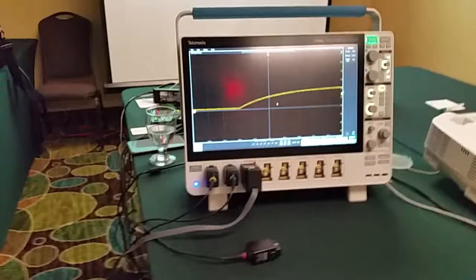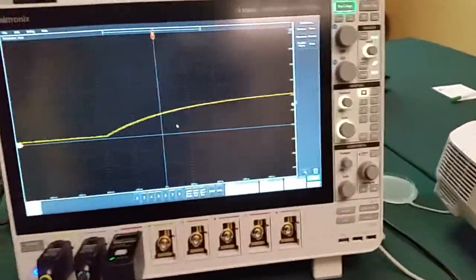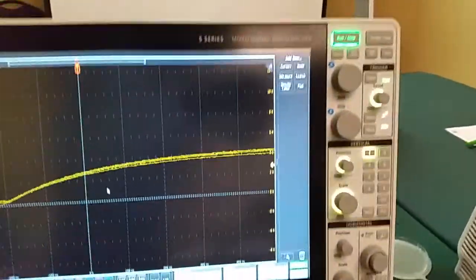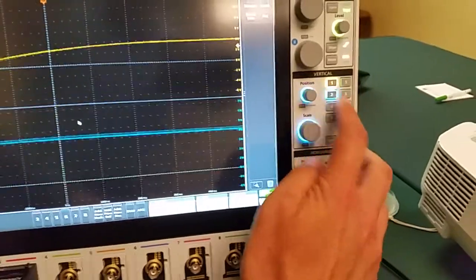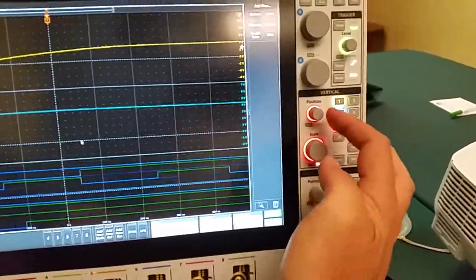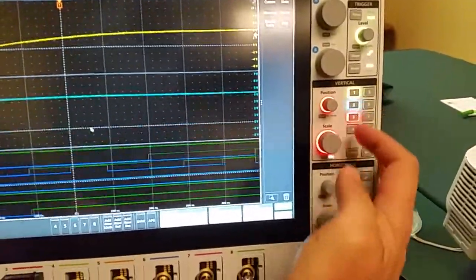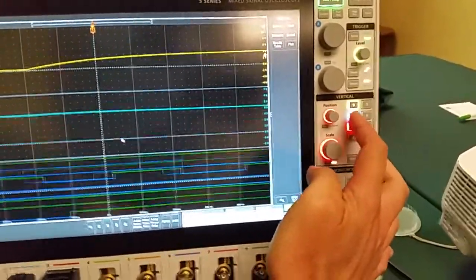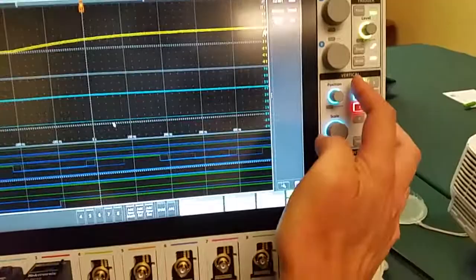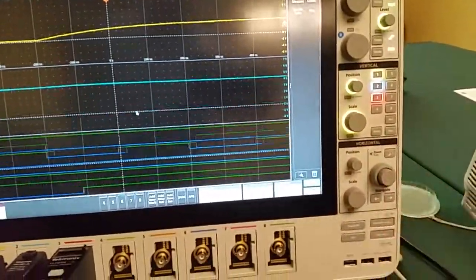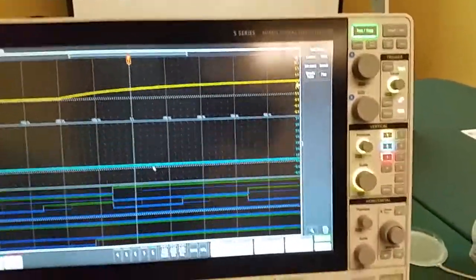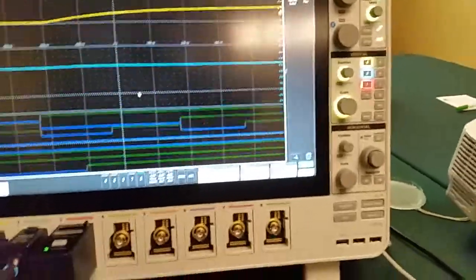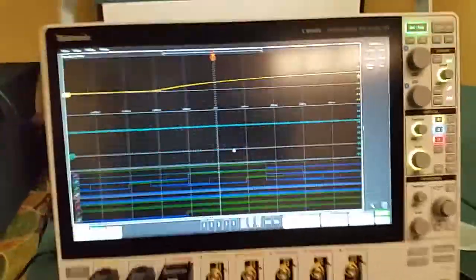So you have eight channels, but yet you have so few buttons. Can you explain how that works? Yeah, so as I turn on channels here, notice that the vertical scale and position knobs are assigned to the channels. So they're red right now, they're on channel 3. If I select 2, they're on channel 2, and so on. It continues through all eight channels here. So it makes it pretty clear of what's turned on by the color coordination.